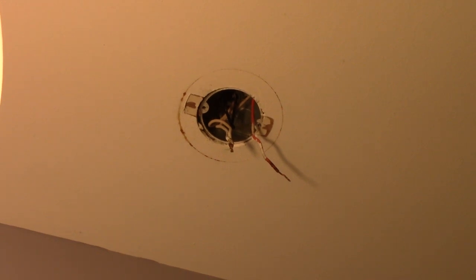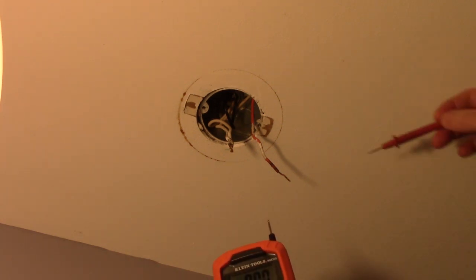I'm going to be installing a ceiling light into a metal box. We're in the Chicago area, so I don't have a ground wire. The metal box is connected to metal conduit all the way back to the service panel, and the conduit is our ground path. When I screw my light into this metal box, the screws will ground the light fixture for safety. And we can confirm that the metal box is grounded by using a multimeter.